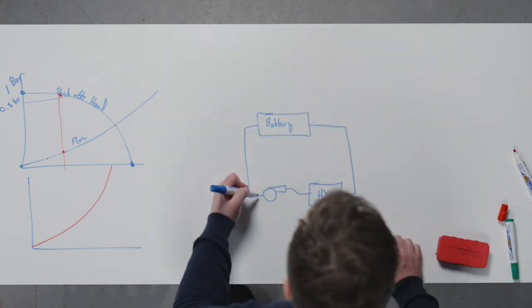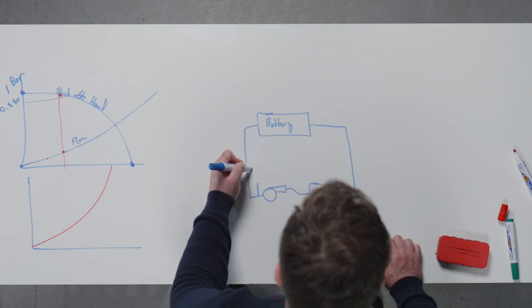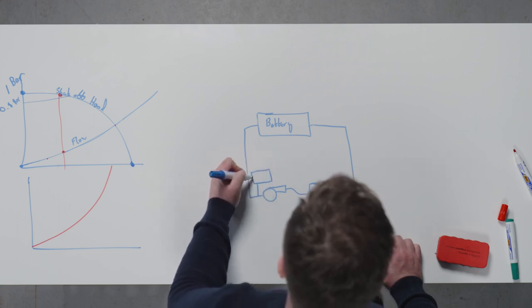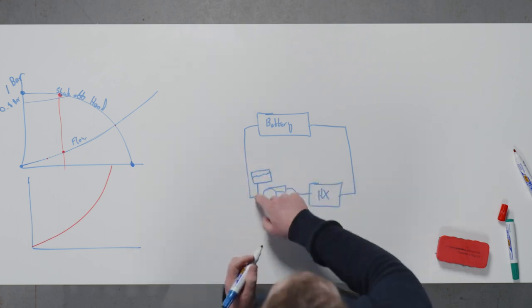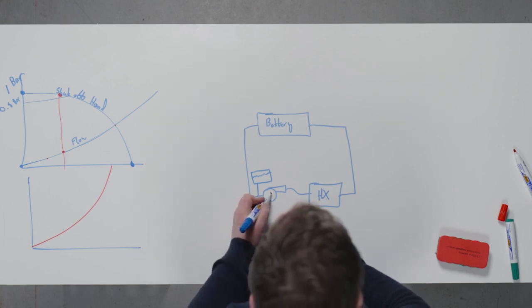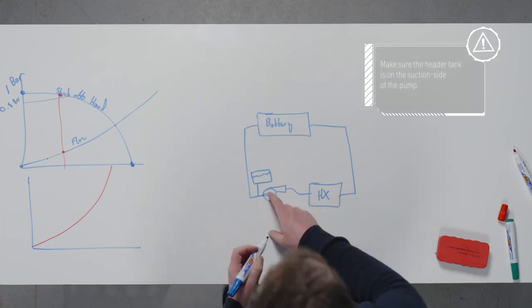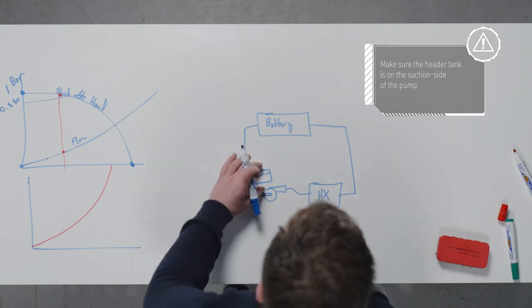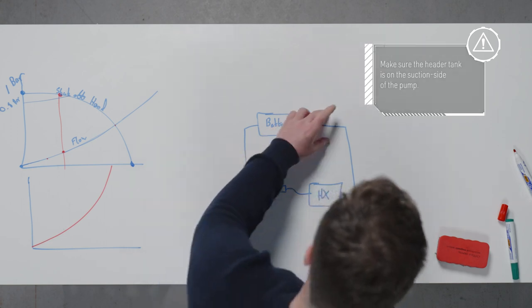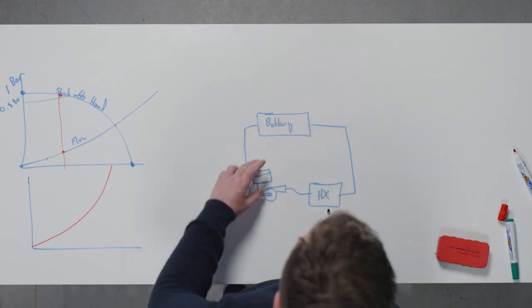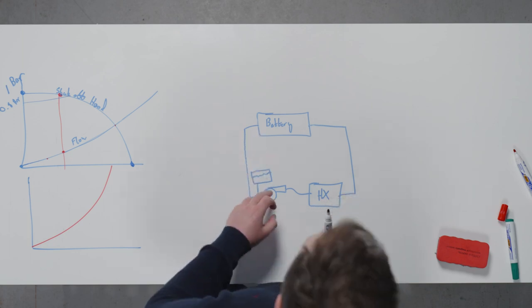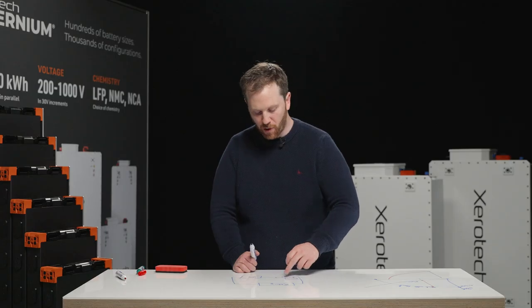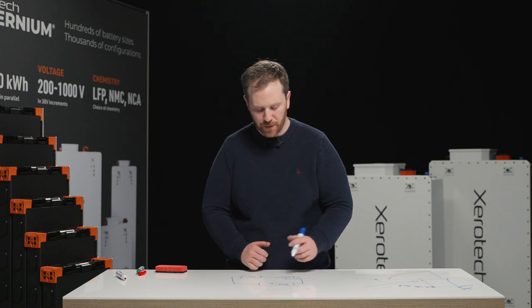The one other component that you would typically add in here is a header tank. And a header tank just simply holds a head of water over the pump, and you always want to put this header tank on the suction side of the pump. It doesn't really matter if it's before the battery or after, but the optimum place is after the battery, just before the pump, so that it'll prime the pump, enabling you to flow through it.